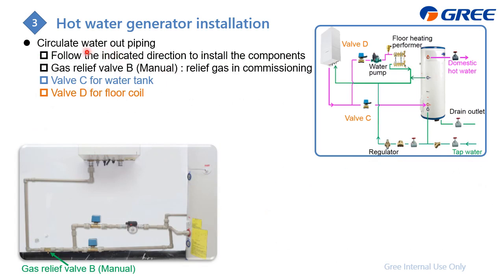Next, we're going to install the circulating water. This time is out, which is the outlet of the hydro box, and we need to supply this hot water either to the water tank from the valve C or to the floor coil from the valve D. And here is the actual piping, which is the outlet of the hydro box, and then from here to the valve C to the water tank, or from the valve D to the floor coil. And also please install this gas release valve B. It is manual. It is also to release the trapped air or gas in the commissioning stage.